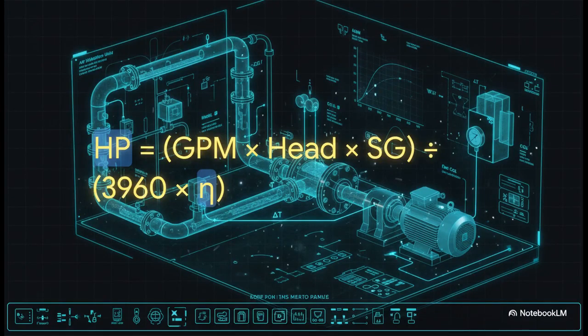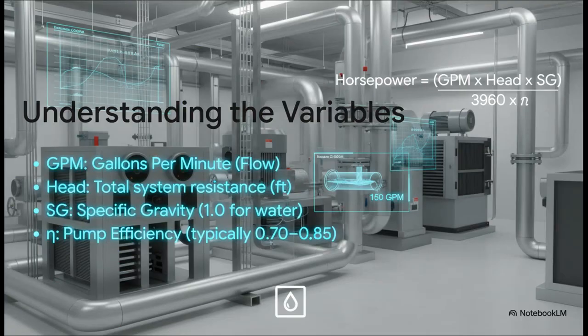And this right here, this is the magic formula that brings it all together. It's the bridge that connects the system's water needs with the raw mechanical power we need from the motor. It takes our flow and our head and spits out the horsepower required. It's that direct. Let's just quickly break this down.